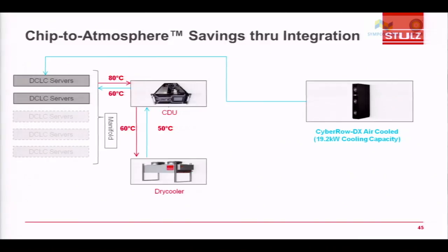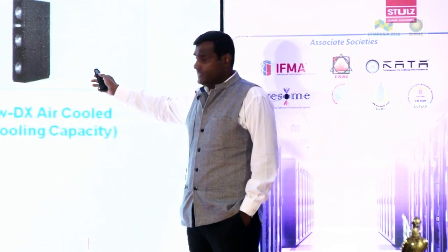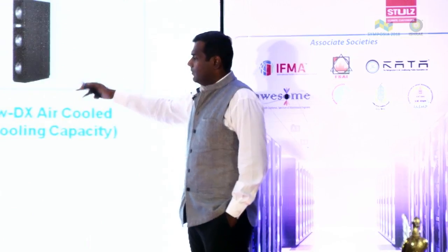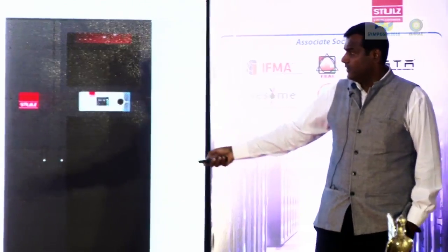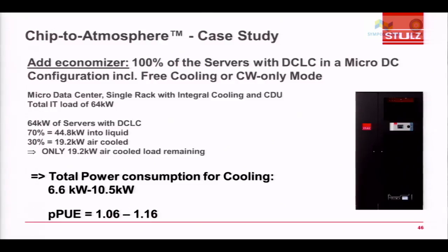So with this, we are completely doing away with power for cooling. It's taken to the next step. We are only using power to run maybe the fans in a dry cooler in an efficient way, and the rest of it is handled with an efficient system. And then you have, of course, we won't lose completely our businesses, we won't be out of business. We would also have a rack cooling, but of a much smaller capacity. So what happens? 70% of the load is taken away by liquid, which is to atmosphere. And 30% of the load would be with our air conditioning equipment. And which means now you substantially better the performance.